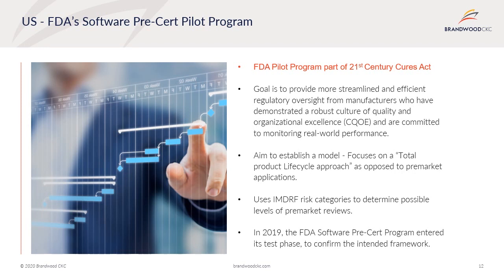The FDA has been at the forefront in trying to address the challenges with regulating medical device software, with the introduction of the 21st Century Cures Act back in 2016. The Act included a section to clarify medical software regulation, especially adding a definition of software as a medical device in line with IMDRF. As a result, a number of changes were made, including changes to existing guidance documents such as off-the-shelf software use and cybersecurity, and publishing of new guidance documents specifically for medical device software, such as guidance for mobile medical applications, general wellness devices, medical device data systems, and artificial intelligence and machine learning. One of the new initiatives was the launch of the software pre-certification pilot program.